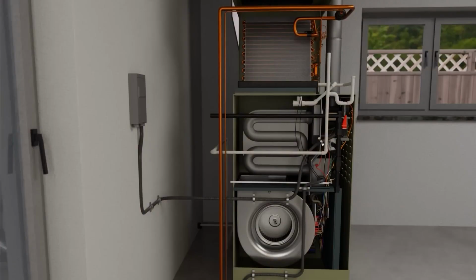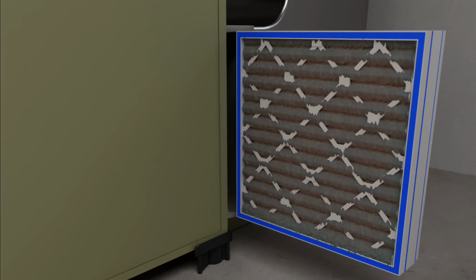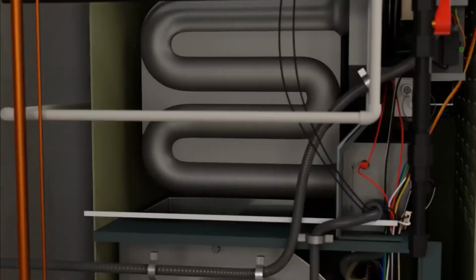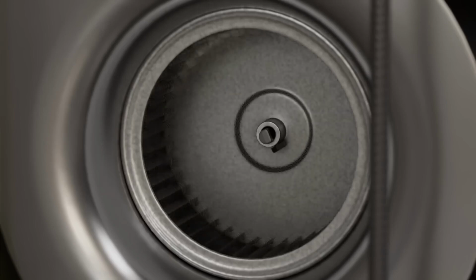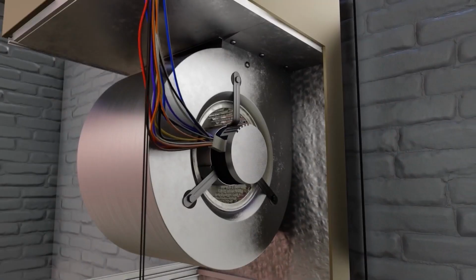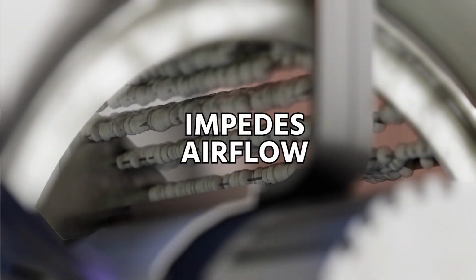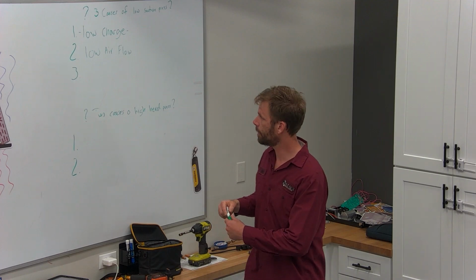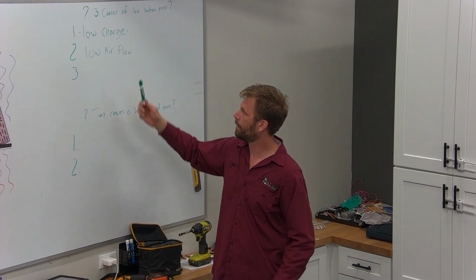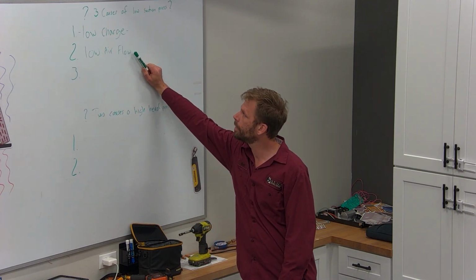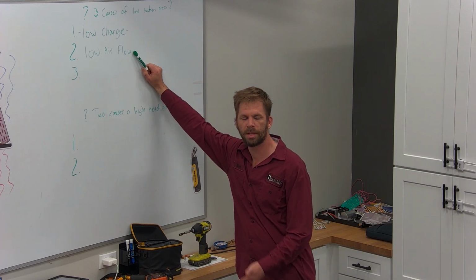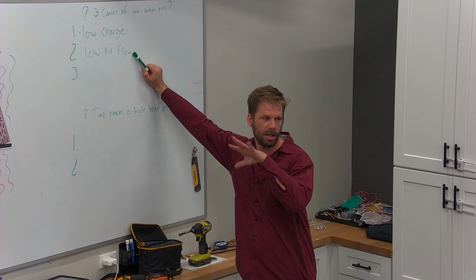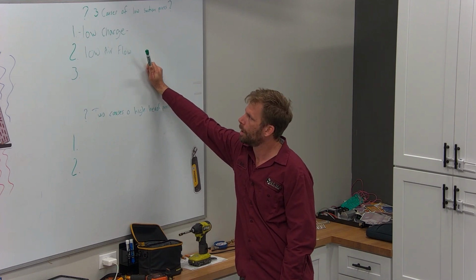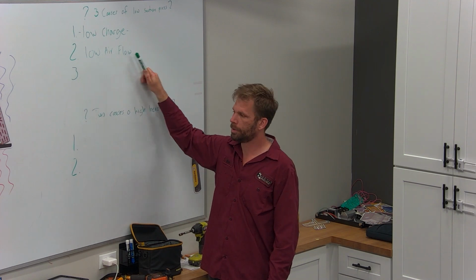Low airflow. There we go. And causes of low airflow, guys. Dirty filter. Dirty coil, dirty filter, blower not working, whatever. Failed blower motor. And another one that is kind of subtle, but fits in the low airflow category for just this discussion, is when the house is really cold. Maybe the same amount of airflow is moving, but there's not nearly as much heat in that air. A better way of doing this would be low load on the coil.